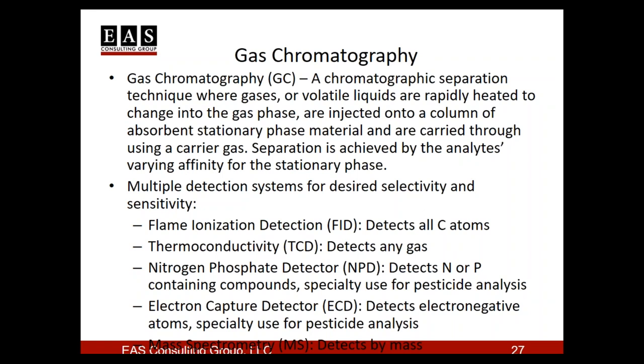A flame ionization detector, or FID, will detect all carbon compounds, so anything organic. A TCD, or thermal conductivity detector, will detect any change in the gas phase flow. Then there are specific types used in environmental labs: an NPD, or nitrogen phosphorus detector, which is specific and very selective for pesticide analysis, and an electron capture detector, or ECD, which is good for electronegative atoms such as bromine and chlorine, often also found in pesticides.